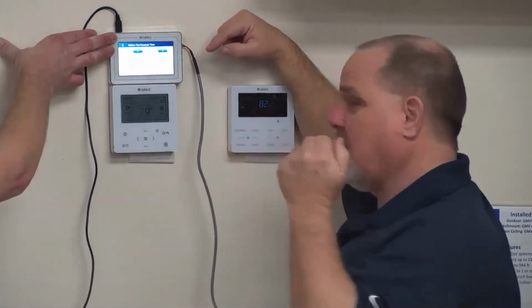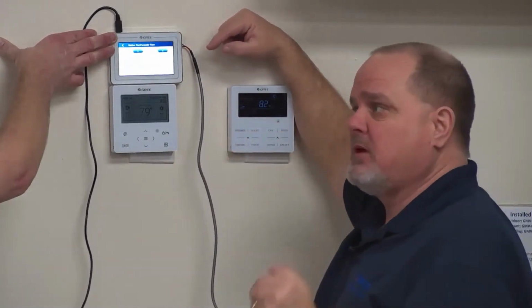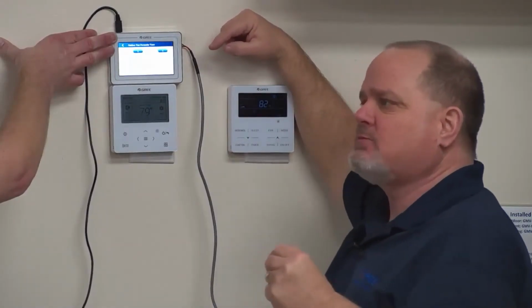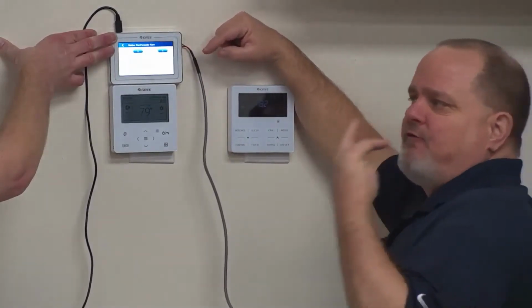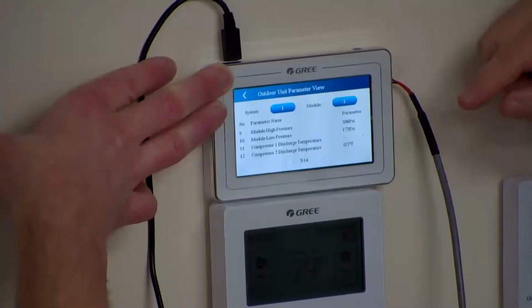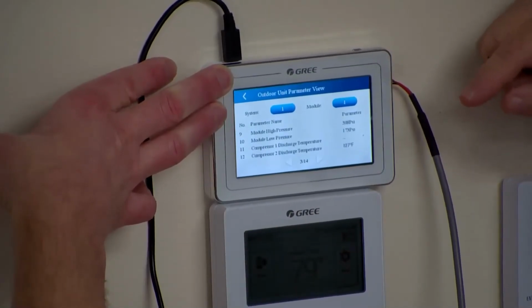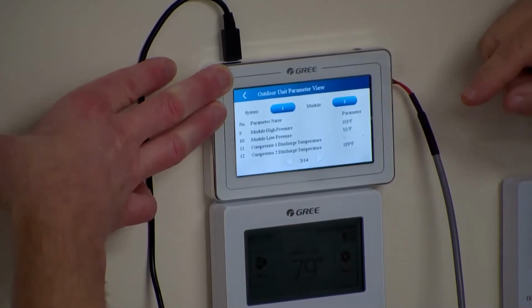Again, that goes back to what I talked about yesterday with the mini split. I may have enough refrigerant in this machine. If I've got 4 indoor units, I may have enough refrigerant to satisfy one, but when I bring in all 4, now I don't have enough refrigerant anymore, and that's why it can't keep up. With all 4, I'm low on gas.